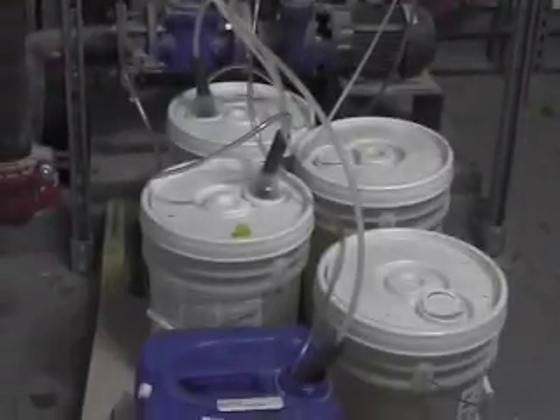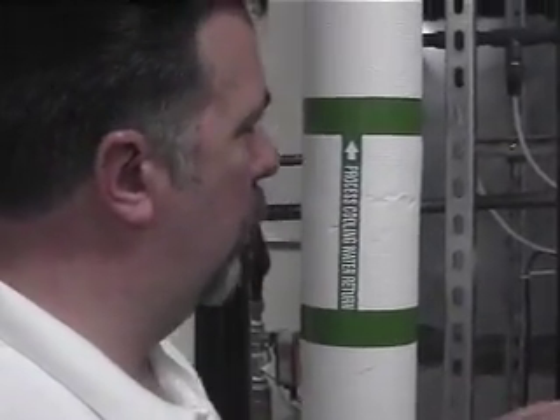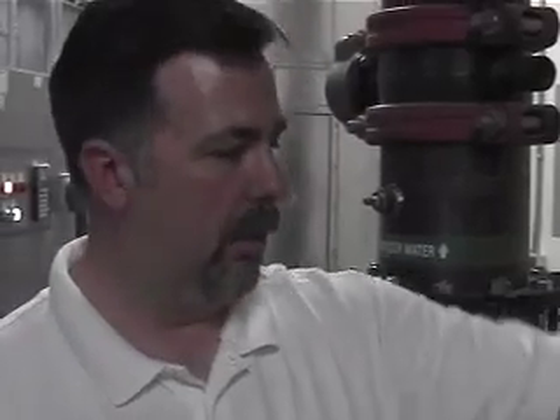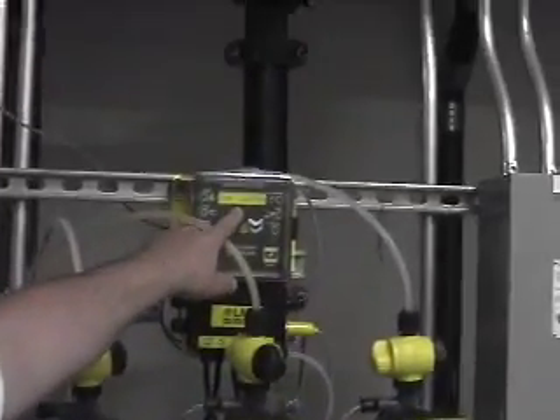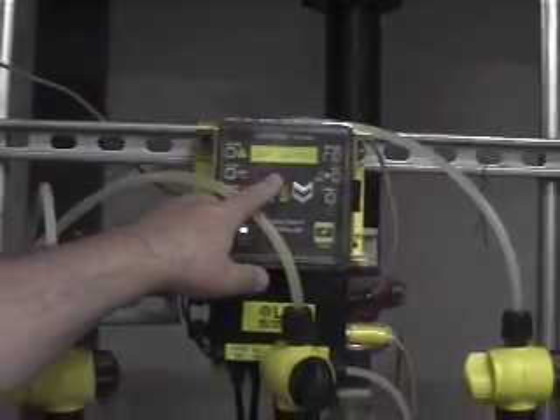This is your chemical feed system for the cooling towers. It pretty much runs all standalone. It's got its own monitoring. It'll inject the chemicals into the water based on the conductivity needs. There's a blowdown valve right here on the condenser water, which is tied directly into the chemical feed controller, so it determines when it needs to open. If you look on the controller, you see your conductivity level display here. So it's trying to maintain, I believe, below 800. If it gets above that, it'll open up the valve.